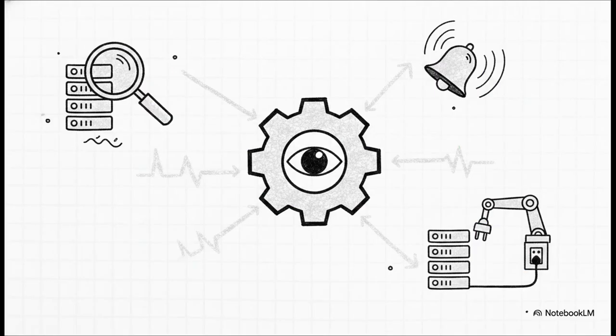But here's the kicker. SCC doesn't just sit there and watch, it acts. Its core capabilities include real-time health monitoring and sophisticated alerting. Think SMTP, webhooks, and direct integrations into ITSM platforms like ServiceNow. But the real magic? That's in its policy-driven automated actions. If SCC detects an environmental hazard, like, say, a coolant leak, it can automatically shut down systems. It can disable smart PDU outlets to instantly isolate affected equipment, and operationally, it manages FRU, Field Replaceable Unit, reconciliation, making absolutely sure you maintain a perfectly accurate asset inventory whenever hardware gets replaced.